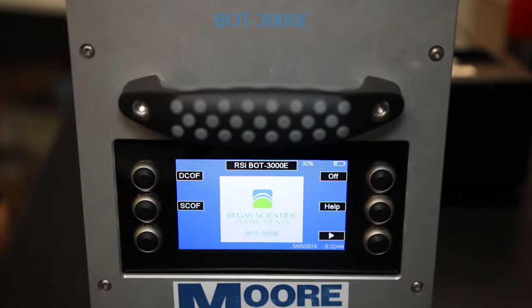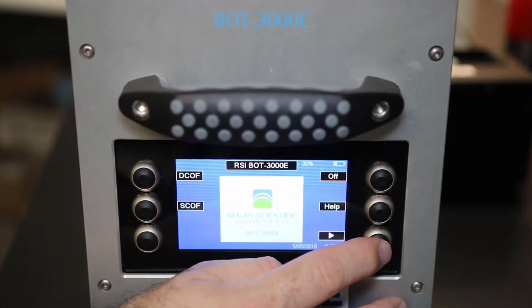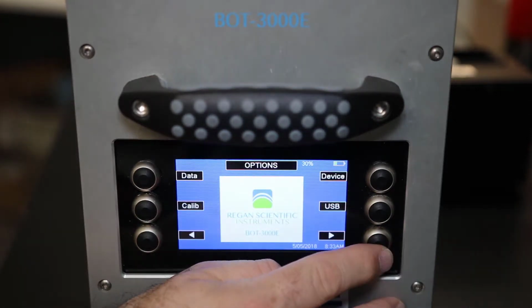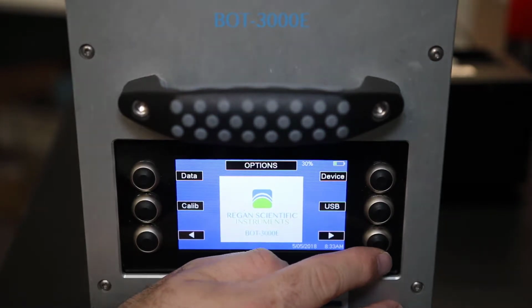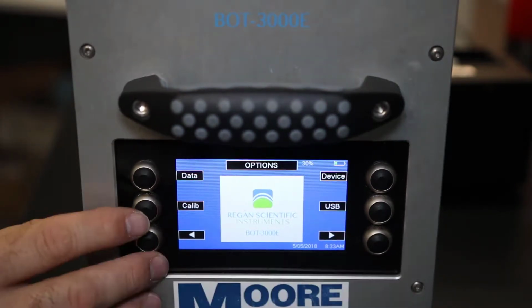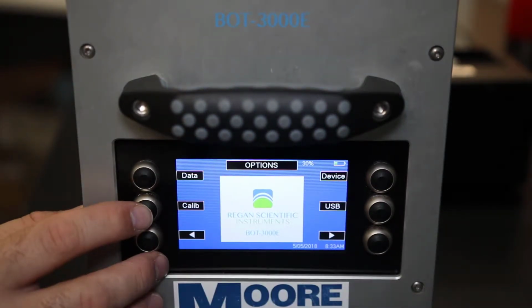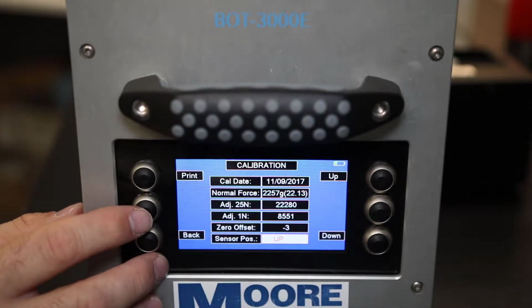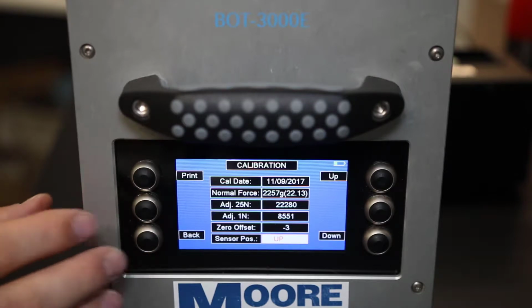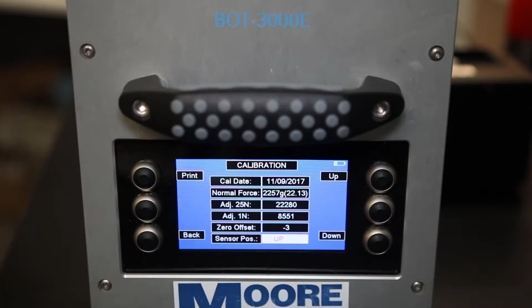To do this, we'll have to scroll to the next page on the BOT screen, where calibration is available. Press the black button next to the arrow in the bottom right-hand corner. At the top of this screen, you'll see options. You'll see Calib as the second option down on the left-hand side of the BOT screen. This page will read facts about the force adjustment, offset, and sensor position. For now, we'll just worry about the calibration date.